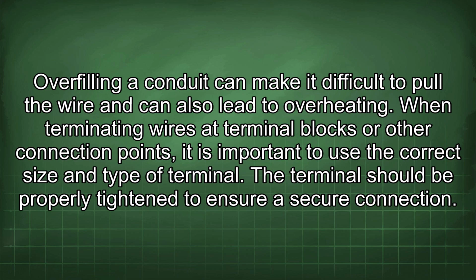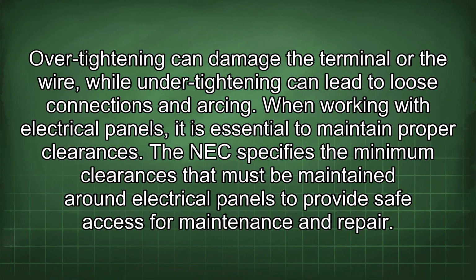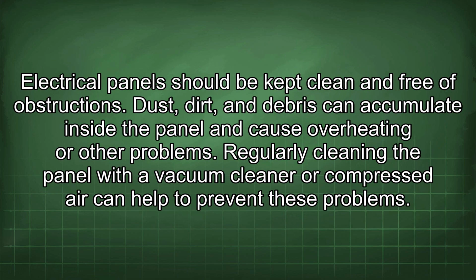The terminal should be properly tightened to ensure a secure connection. Over-tightening can damage the terminal or the wire, while under-tightening can lead to loose connections and arcing. When working with electrical panels, it is essential to maintain proper clearances. The NEC specifies the minimum clearances that must be maintained around electrical panels to provide safe access for maintenance and repair. The electrical panel should be kept clean and free of obstructions.